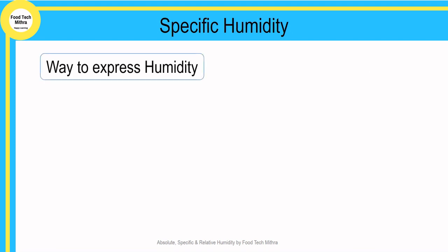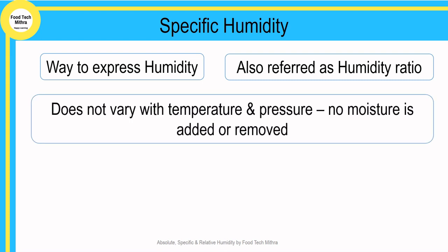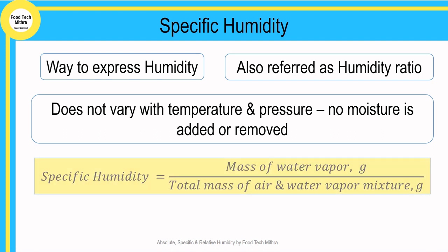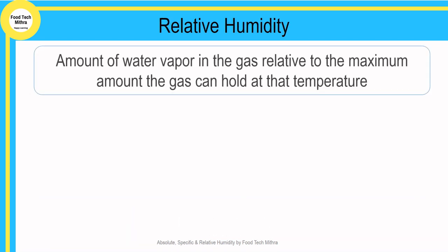Specific humidity is another way to express humidity and is also referred to as humidity ratio. Specific humidity is given as the ratio of the mass of water vapor to the total mass of the air and water vapor mixture. It does not vary with pressure or temperature as long as moisture is not added or removed from it.